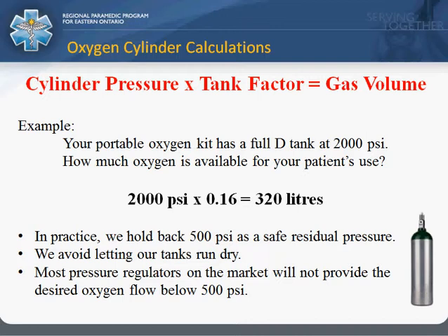And that gives us a little bit of wiggle room if we're not 100% ready to actually change the tank right at that second. The second item is more of an oxygen supplier problem, but we never want to let tanks go completely dry. As soon as you let every drop of pressure out of that tank, there's an opportunity for moisture to get inside the tank, and that's a problem for the suppliers. So we try to help them out and not let the tanks go completely dry.